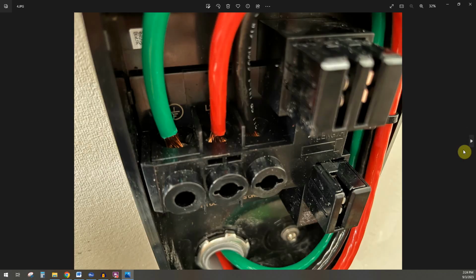Another tip I've never seen anybody mention is the insulation. Everyone always talks about stripping the insulation to the right length. That's great and all, but on top of that, you also want to make sure that you don't have any insulation in the terminal or in the lug specifically. As you can see here, just a little bit of insulation is sticking out of the terminal. That's because I want to make sure there's no insulation torqued down on the lug. If that happens, it's going to melt and you're going to start a fire that way. So I like doing it like this, where you can just see a little bit of it, to make sure you're good.